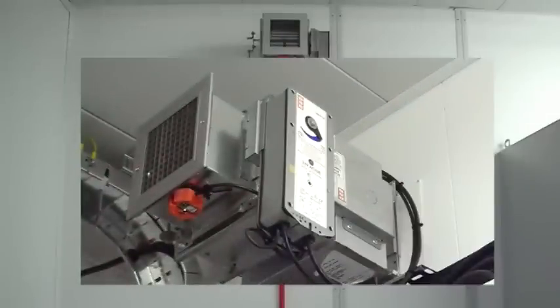Pressure relief dampers are fitted at all outlets to maintain an internal positive pressure of 50 pascals. This helps to prevent ingress of sand, dust and flammable gases. In addition to the pressure relief dampers, fire dampers are fitted to all inlets and outlets and operate to close on confirmation of a fire.